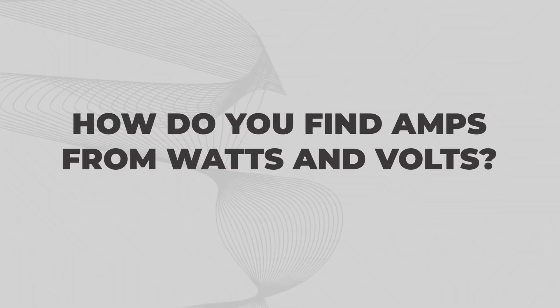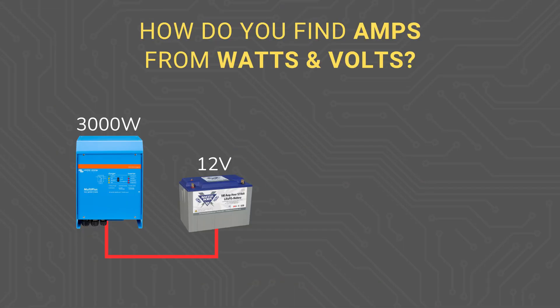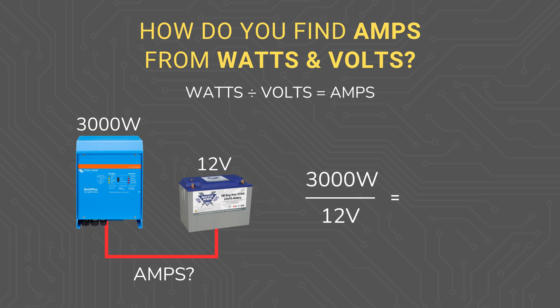How do you find amps from watts and volts? Let's say that you have a 3000 watt inverter powered from a 12 volt battery bank and want to know how many amps you can anticipate flowing through the wire from the battery to the inverter to size that wire. For that, you would take 3000 watts divided by 12 volts, which gives you 250 amps.